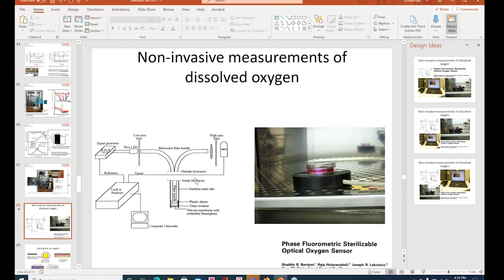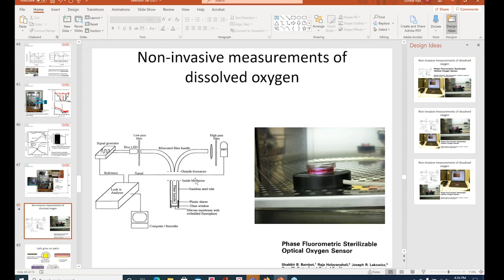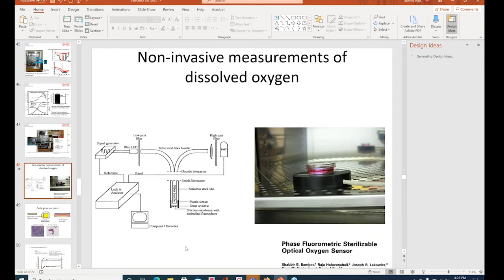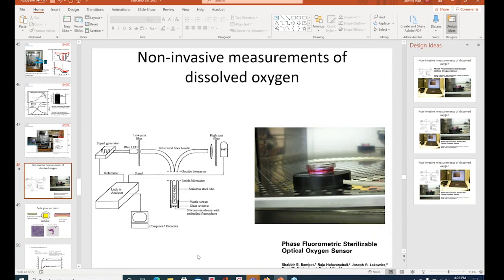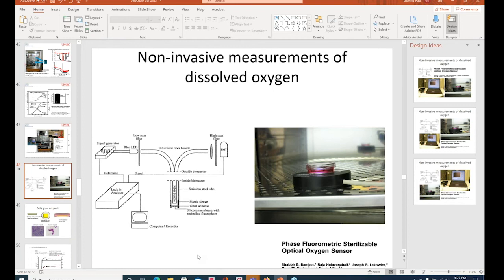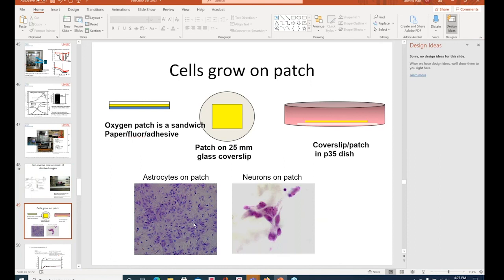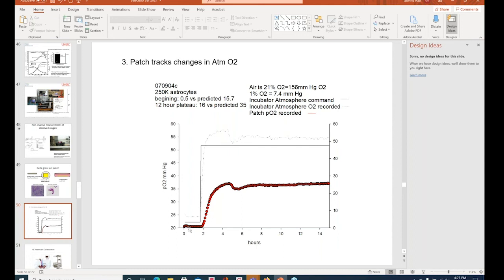This is a piece of history. We've built our first version of the optical sensors that could go into a bioreactor. And the reason we did that is I was invited by what are today multi-billion dollar biotech companies that were small then in the early nineties, and they were struggling to measure oxygen. They said, these oxygen electrodes don't work. We put two of them in a 30 liter bioreactor, and one's giving one reading and others given another reading. So I was like, what do you tell the FDA? And they sort of said, don't tell anyone, but we don't report it at all. We just keep this for internal use. So they really had a problem and that really spurred the development of this optical alternative. We've grown astrocytes and neurons and basically take home message that you may think that your incubator environment is dialed into a particular oxygen level, but because of diffusion limitations, what the cells see is very different.